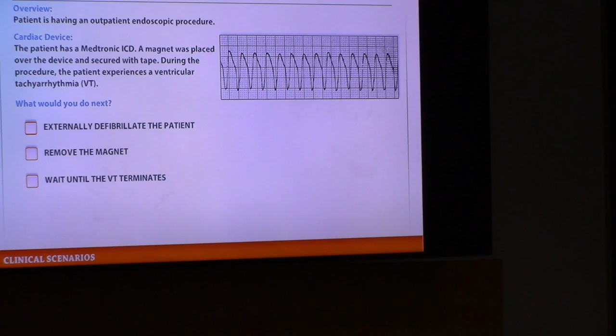And now I'm going to show you what happens to the ICD. So now you're putting a magnet. You'll hear that tone. You hear this long tone, meaning that it's right on top of the device. Okay? And then it'll stop. And then it means that you've placed it right on the device and now all the therapies have been suspended. Within taking the magnet off, like 2 seconds after taking it off, it will return back to normal. Okay? It will start detecting arrhythmias and all of that.